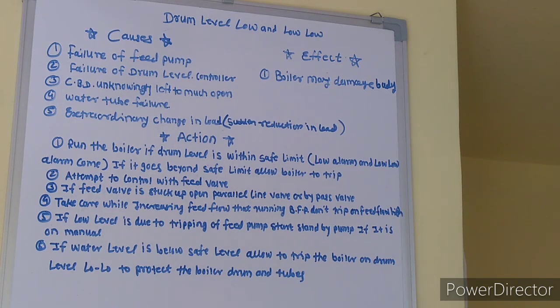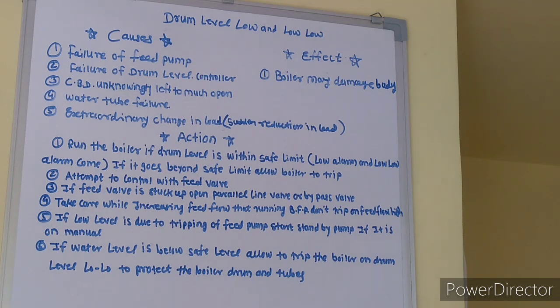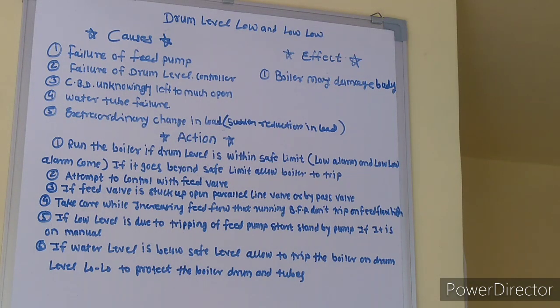Now let's discuss actions. Run the boiler if drum level is within safe limit — low alarm and low-low alarm have come. If it goes beyond safe limit, allow the boiler to trip. Attempt to control with feed control valve. If feed valve is stuck, use parallel line valve or bypass valve. Take care while increasing feed flow that the running BFP does not trip on feed flow high.